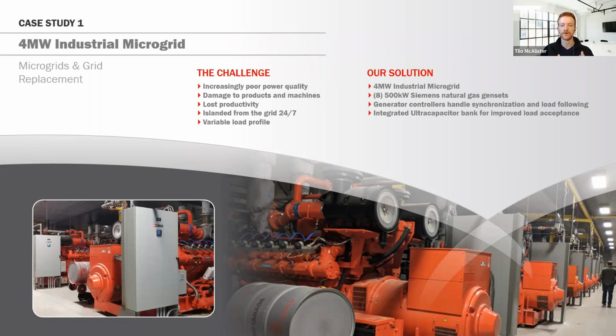So the way we designed this plant was with 8 roughly 500 kilowatt natural gas engines, so that according to their production schedule, we maybe only run several of these units to supply the load, and they're all controlled and operated together to share that load as needed. When there's higher demand, they can ramp up and down, and maybe they're all working, but pretty much always we're able to have one down for routine maintenance or an unplanned shutdown without disrupting operations in their production plant.